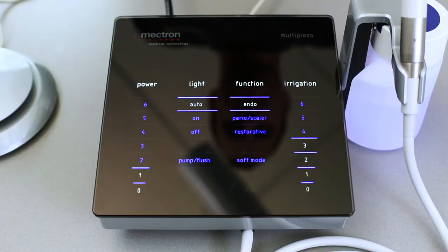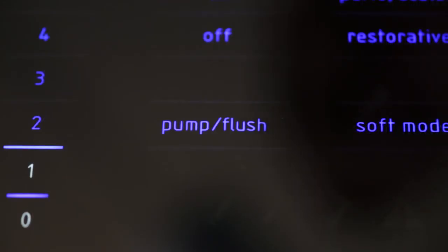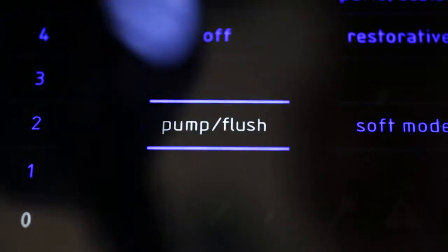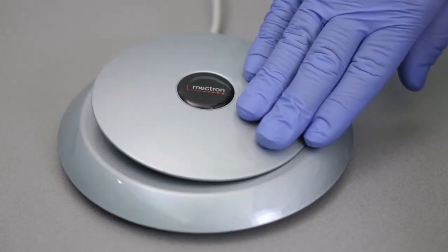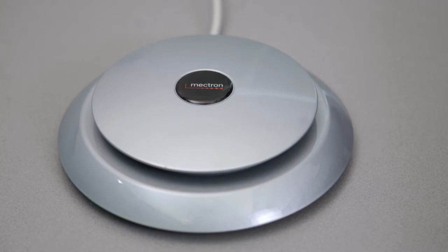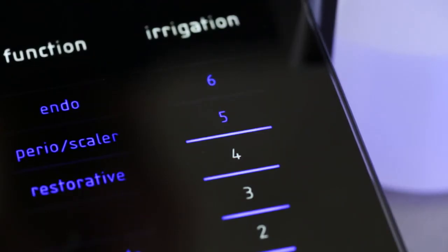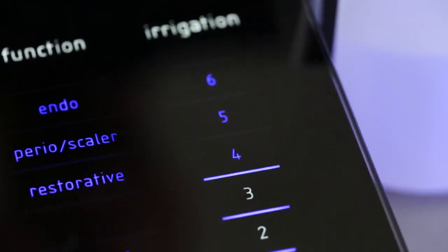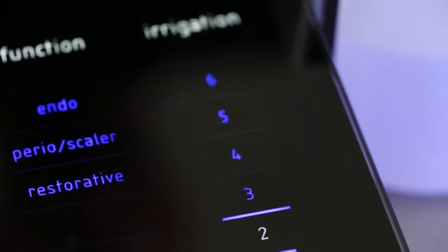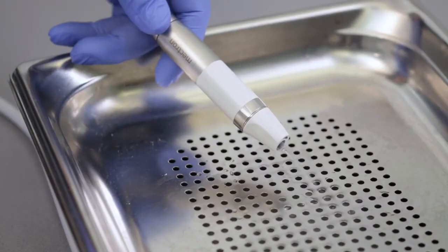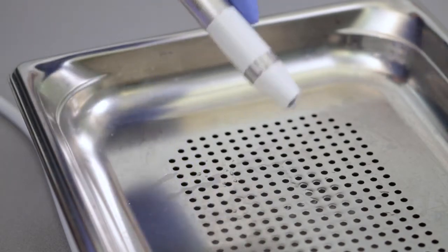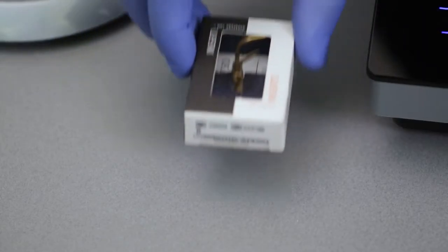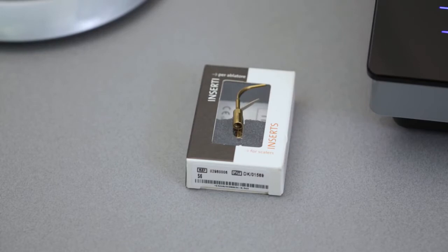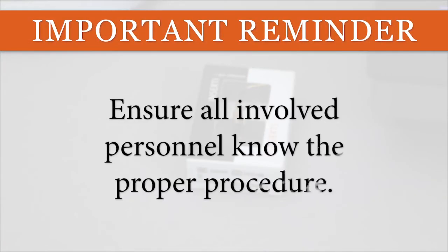Looking at the glass touchscreen, you'll see the words Pump Flush illuminated near the lower left corner. Touch this and then tap the foot pedal once to initiate the pump flush cycle. This cycle will start at an irrigation setting of 6 and automatically decrease until it shuts off when the flush is completed. The entire cycle lasts approximately 20 seconds. Next, we will practice installing and removing the insert tips. It is important that this step is practiced by all involved personnel to ensure that everyone knows the proper procedure.